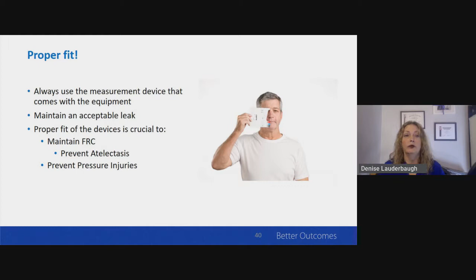Now we're going to talk a little bit about patient mask leak. This is a parameter measured in liters per minute of the amount of flow that comes out between the non-invasive ventilation mask and the patient's skin. This amount of unintentional leak is affected by the tension that you apply to the straps that secure the headgear, and they hold the mask in place. The more tension that you apply to those straps, the tighter the mask is on the face, and the smaller the patient mask leak will be, putting increased contact pressure on the skin.